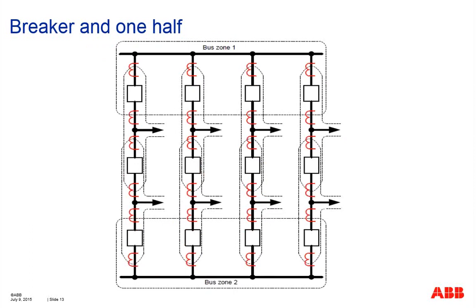So basically, for this type of bus configuration, you need dedicated bus protection for each of the two main busbars, on the top and on the bottom. And for the other busbar, we call that the stub bus. These stub sections are typically already properly protected by the equipment protection, by overlapping the two CTs.